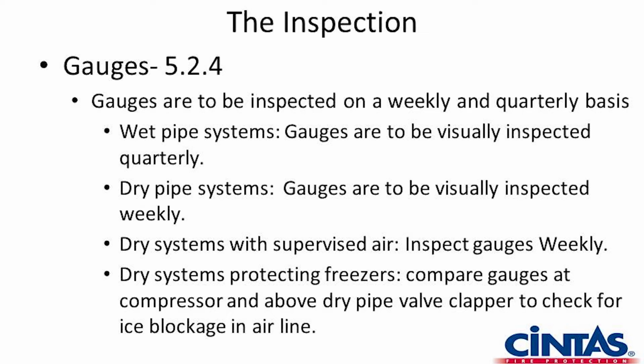That's a little bit confusing for folks right there, but we're talking about when we have a dry system that is protecting, say, a walk-in cooler. The temperature difference between the cooler and where the air pressure is coming from, because of that condensation that would build up in our temperature, can actually freeze and form an ice plug in the piping. We can check our gauges because we have one on either side and compare what that air pressure is. If there's an ice block there, those won't read the same pressure or close to the same pressure. And that would be a key indicator that we do have an issue with an ice plug in the system.